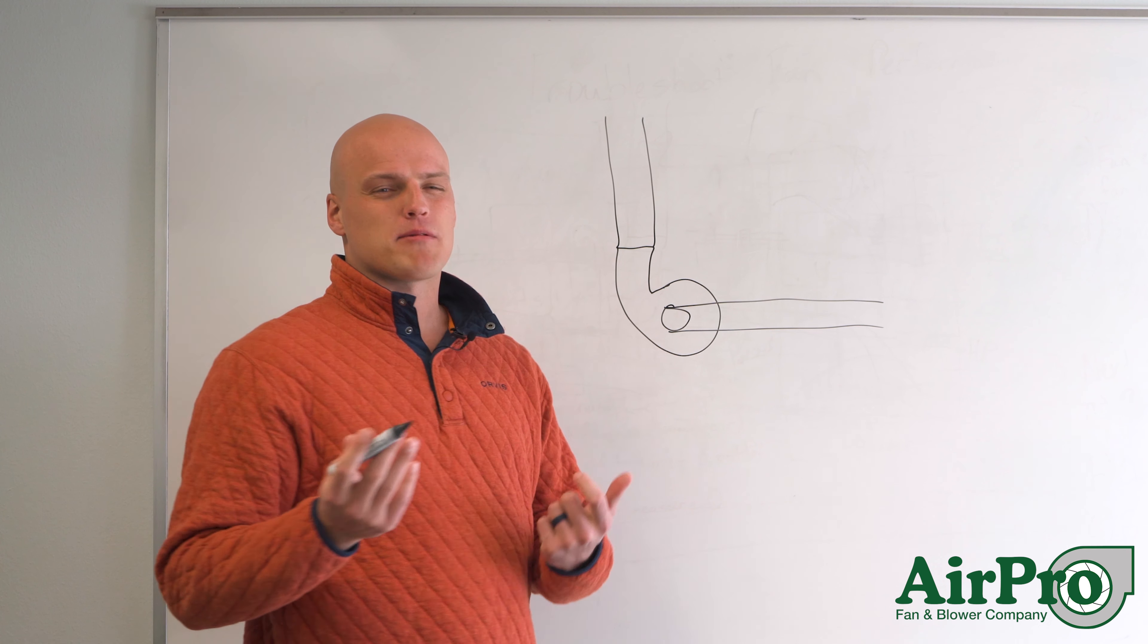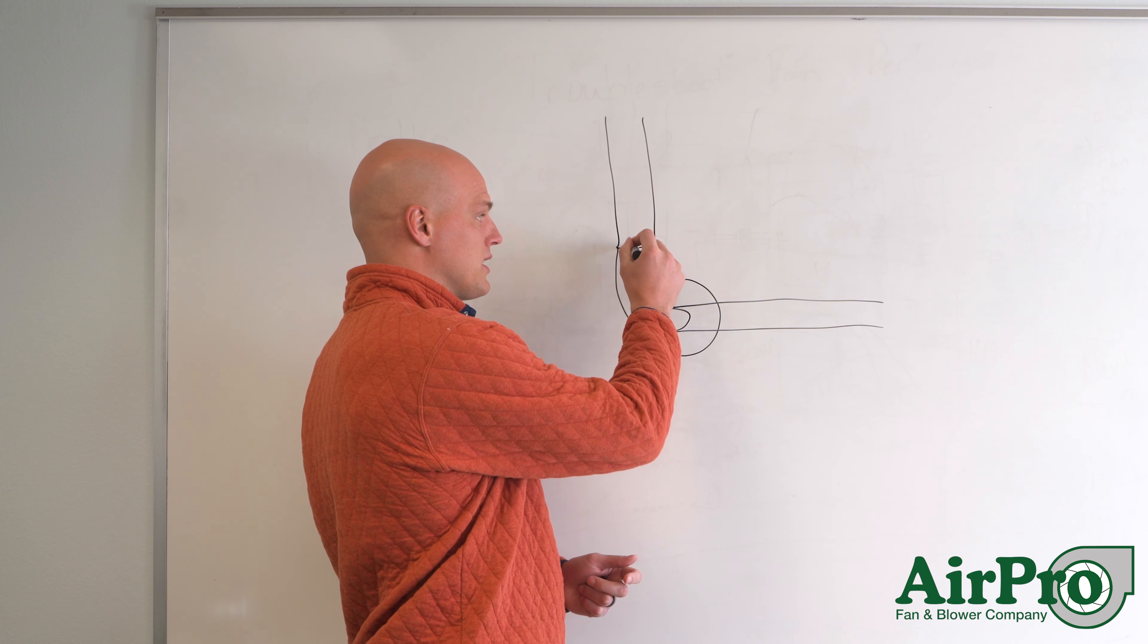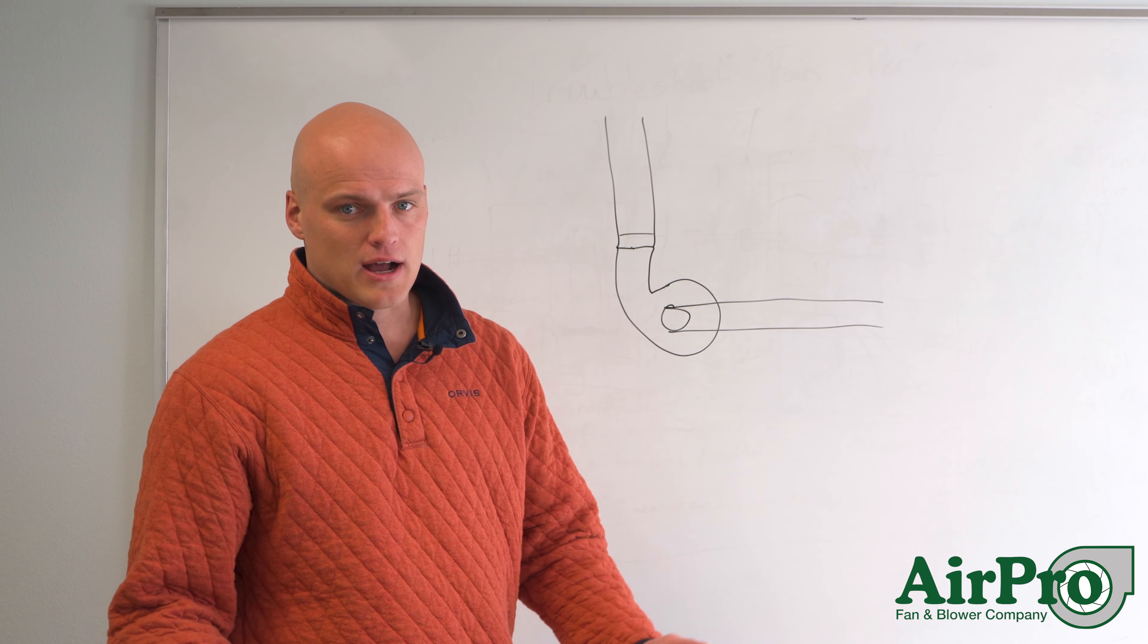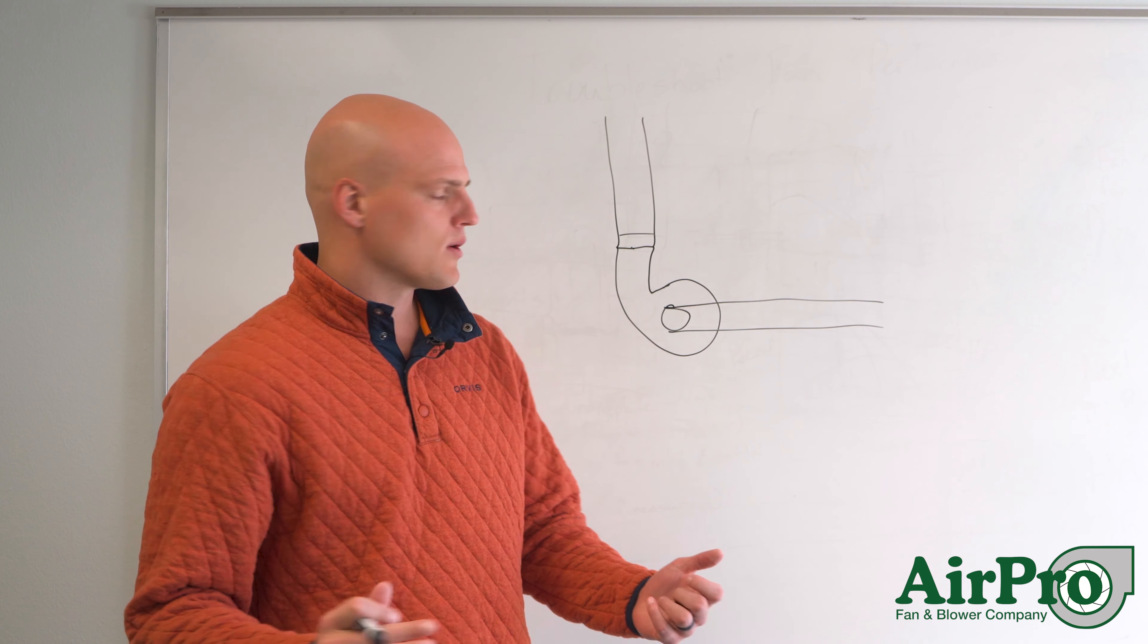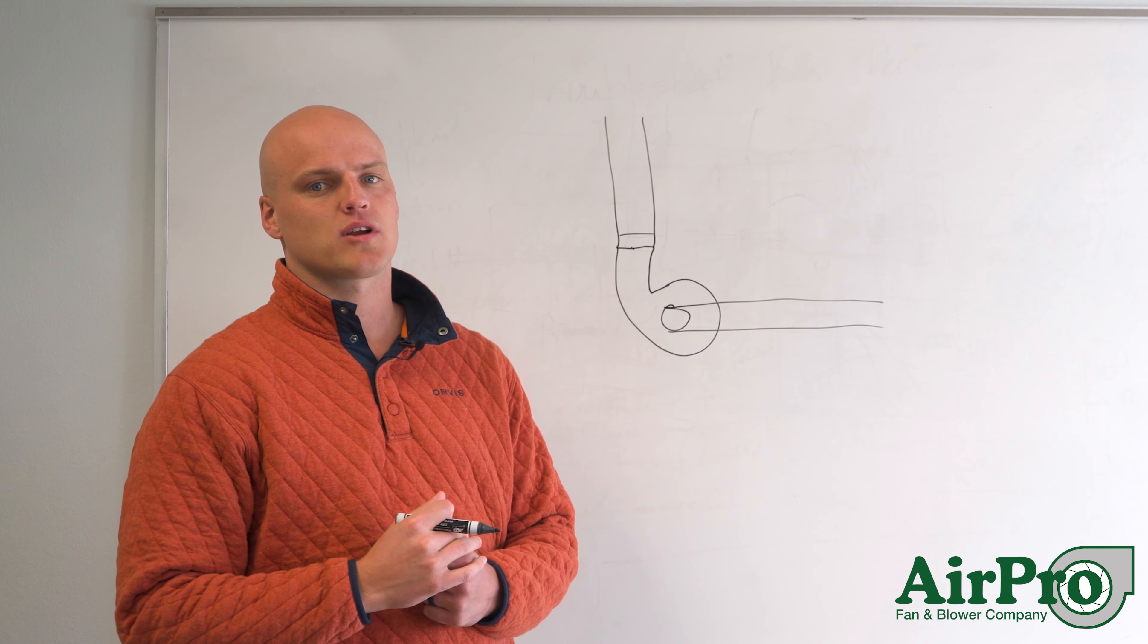So where we would probably look to put this, if you're just looking to resist flow in the field, I recommend putting it on the outlet of the fan. And all you're looking to do is create a blockage in the airstream. So an opposed blade outlet damper right here can help add some pretty quick resistance.